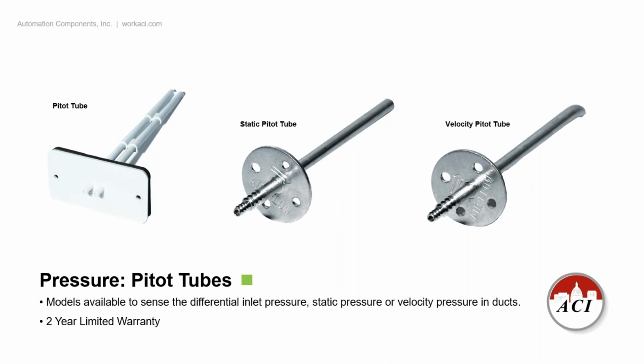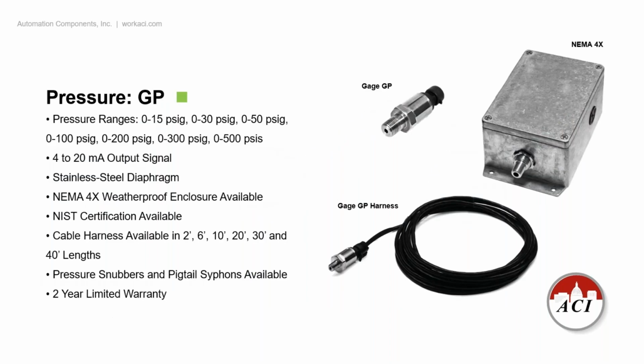Other optional pitot tubes or pickup ports can be used for static, velocity or duct. Just another mounting feature that could be used on the high-low barbs of the actual transmitter or switch itself, connecting the tubes together. Excuse me. So that covers the dry side of pressure.